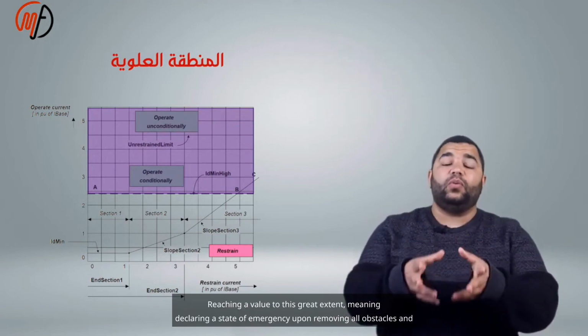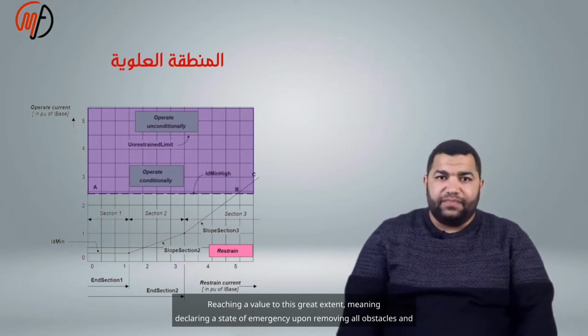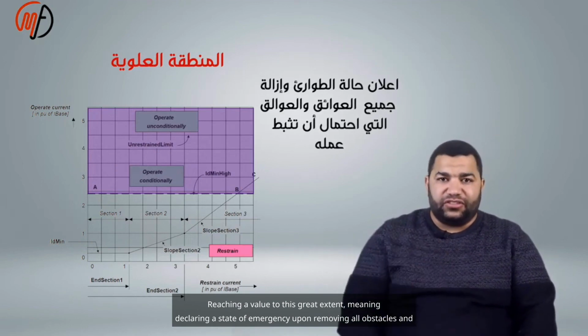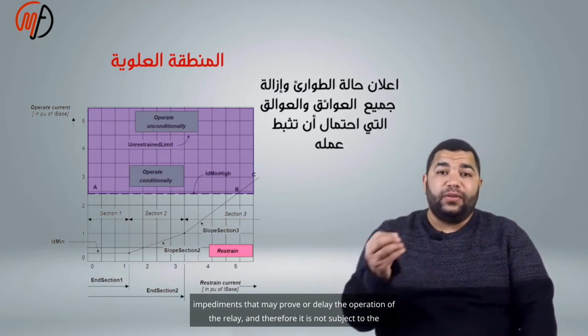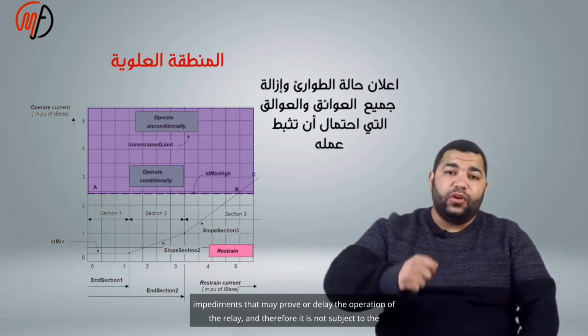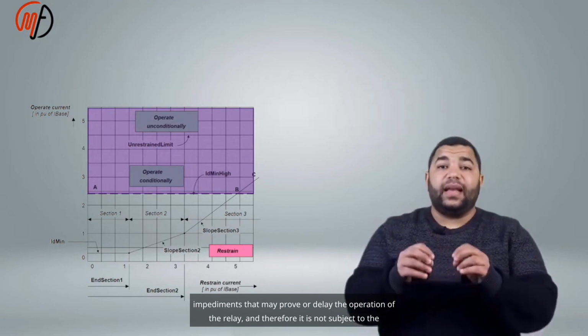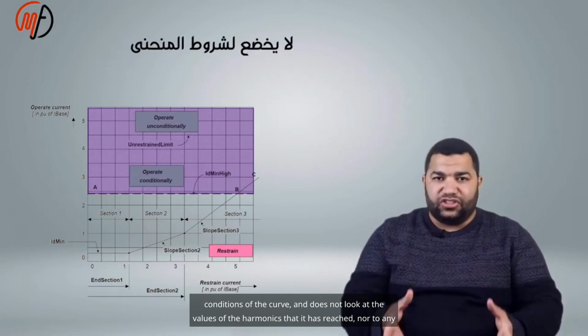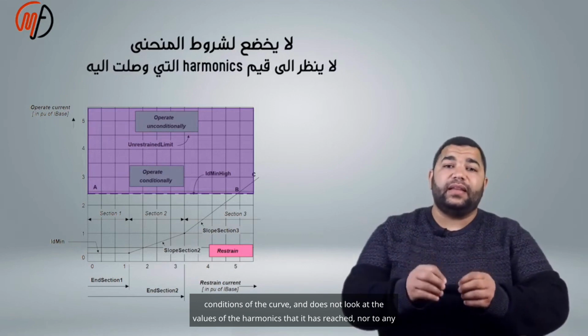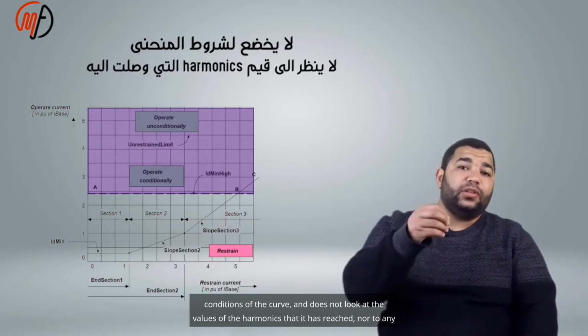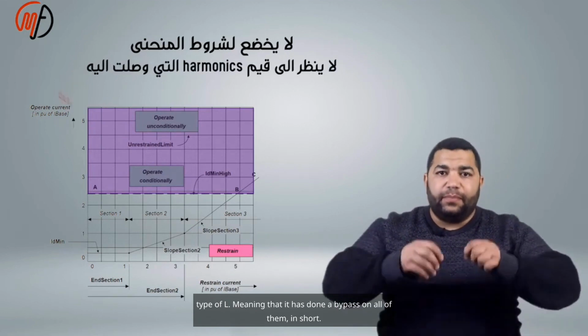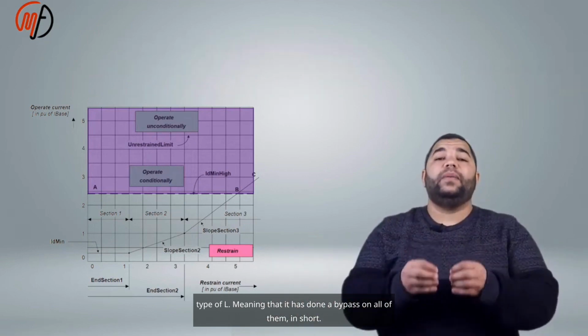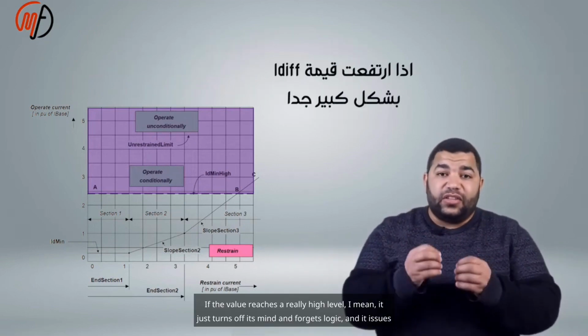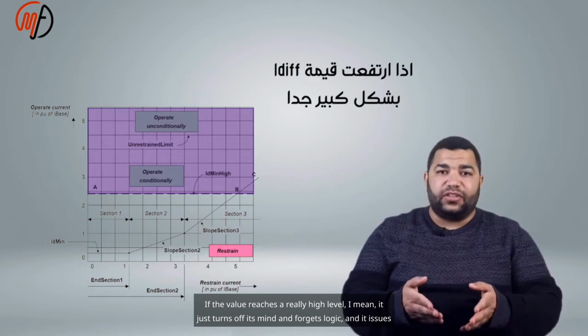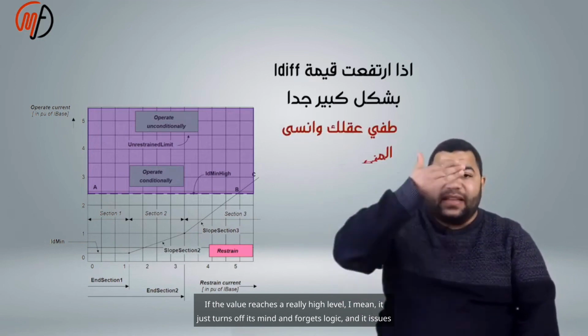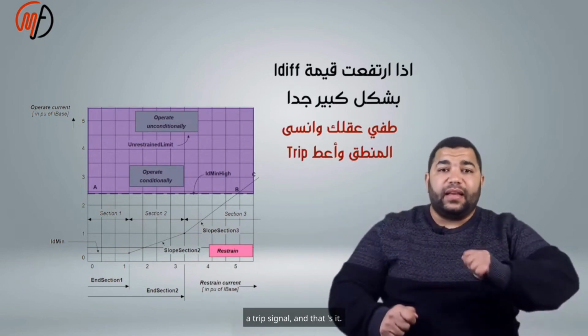It is also referred to as reaching a value to this great extent, meaning declaring a state of emergency, removing all obstacles and impediments that may prove or delay the operation of the relay, and therefore it is not subject to the conditions of the curve and does not look at the values of the harmonics that it has reached, nor to any type of restraint, meaning that it has bypassed all of them. In short, if the value reaches a really high level, it just turns off its mind and forgets logic, and it issues a trip signal, and that's it.